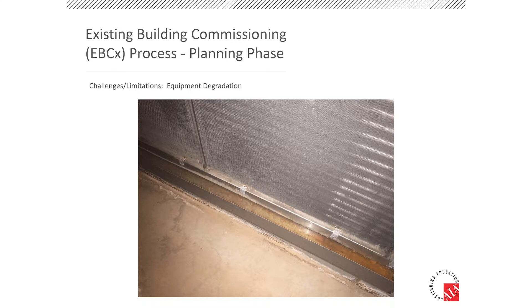What you're seeing here is a drip pan underneath a coil inside the air handling unit, obviously hasn't been cleaned in a while. We also found a lot of debris inside the coil itself. Maybe the drip pan doesn't get at the issue of temperature and humidity control, but if you have a coil that doesn't have a free flow of air, that could certainly have something to do with it. This is another good example of equipment degradation over time.